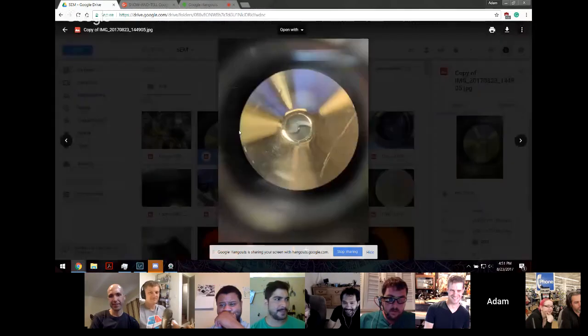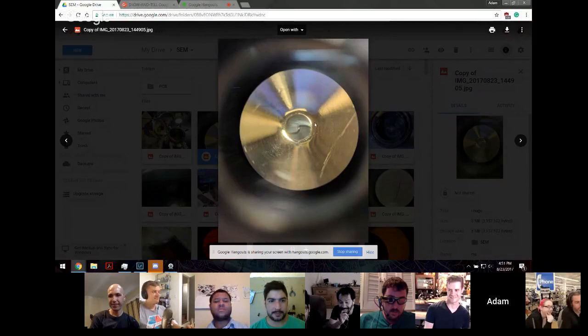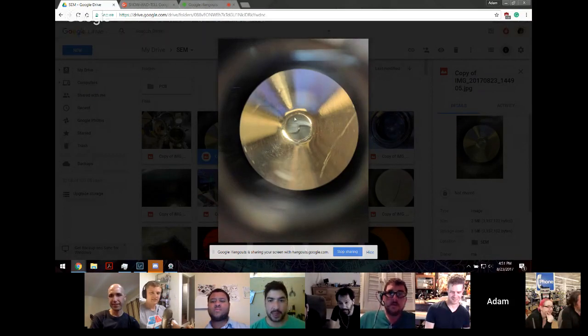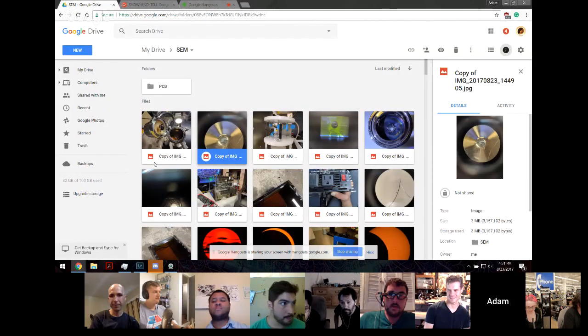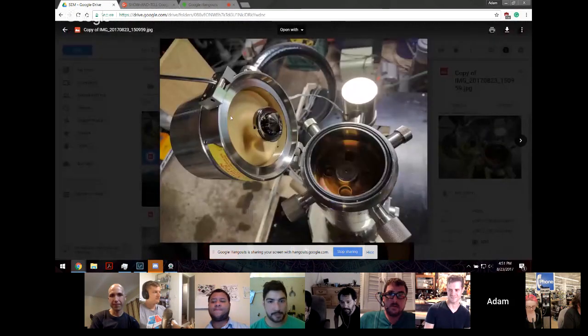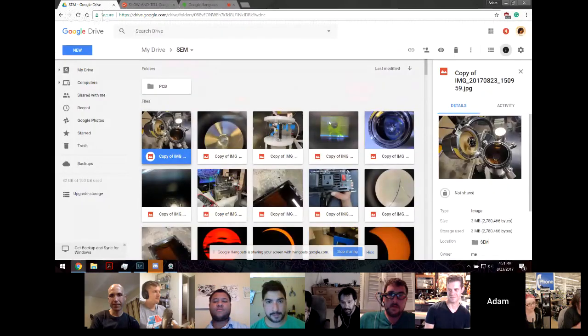But anyway, I had to replace that. And replacing this is way harder than I thought it was. You have to perfectly align the filament inside of the anode cage. And we're talking within a thousandth of an inch. And you have to do this visually with set screws. So that took a really long time. I didn't think it would take that long, but I got it mounted back up at the microscope, powered the SEM back on, and I got this.